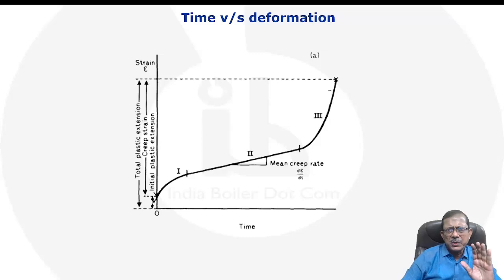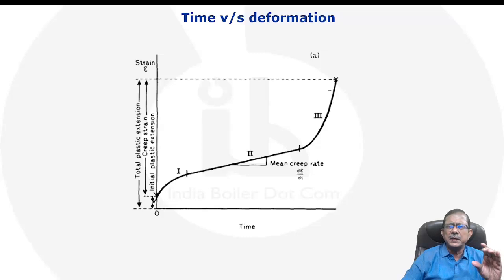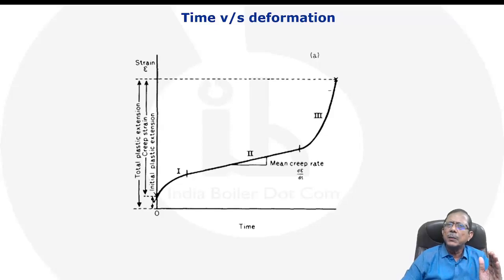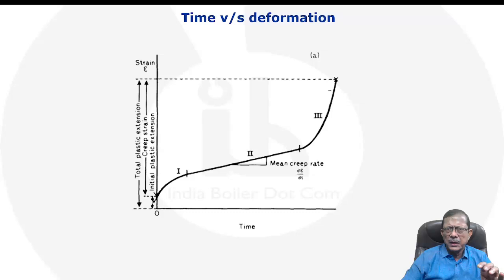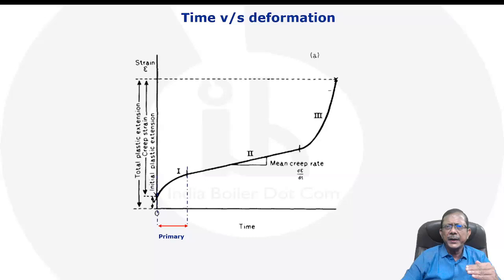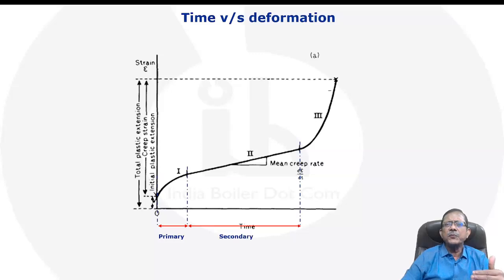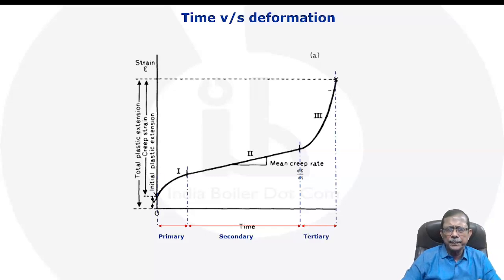Looking at the creep curve — a time versus deformation curve — initially there is rapid deformation in almost the elastic range, after which plastic deformation starts. Initially the rate of deformation against time is faster; this is called the transition zone or primary creep. After that it becomes much more steady for a long time — the secondary creep. After that, tertiary creep initiates, and then very fast it reaches the failure portion.